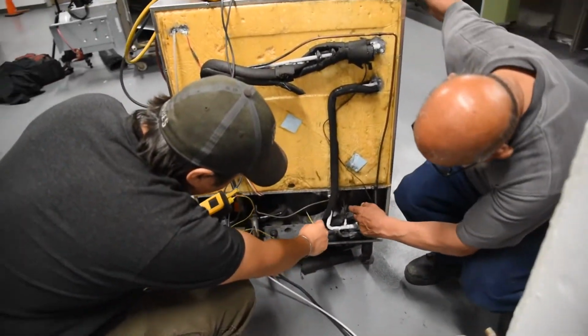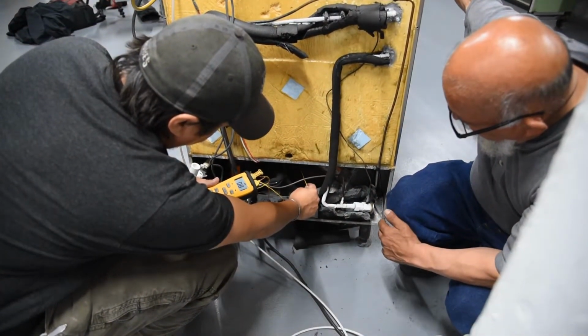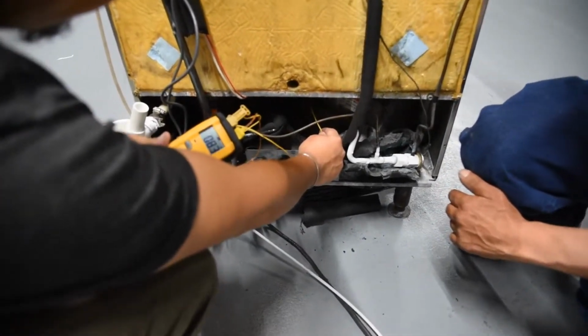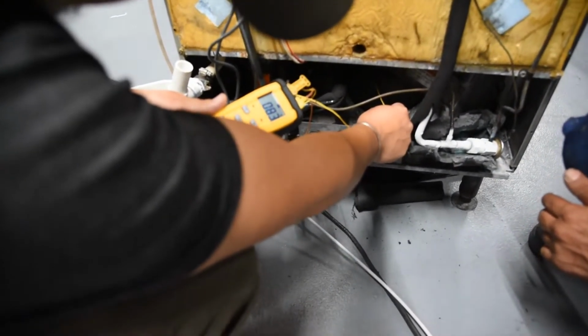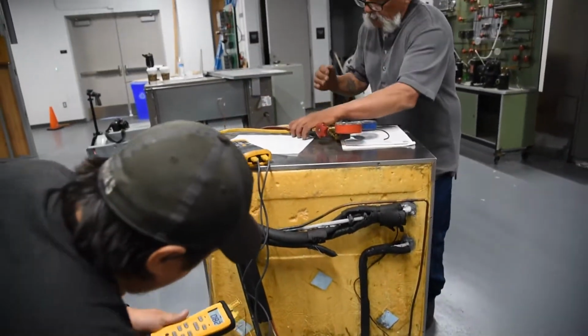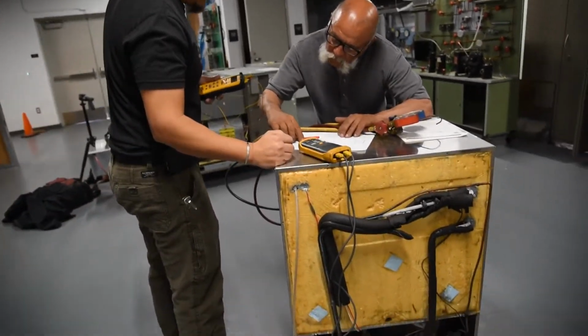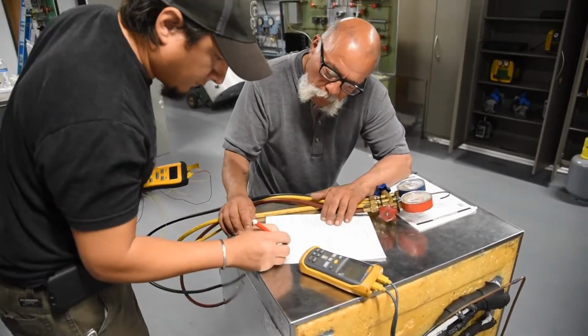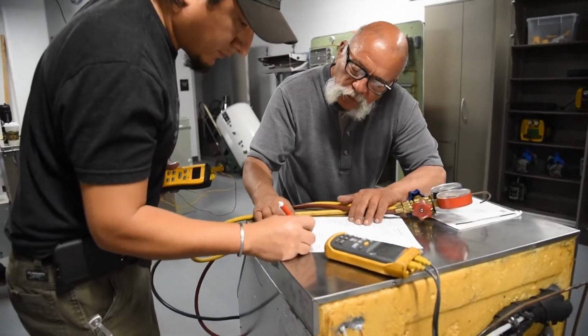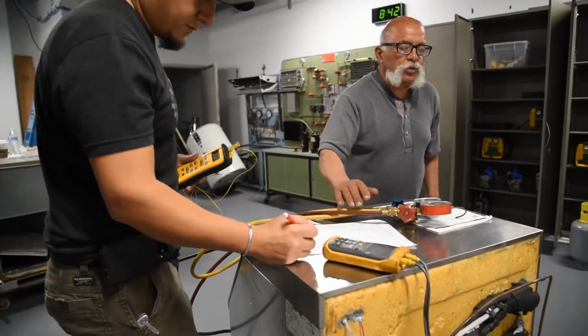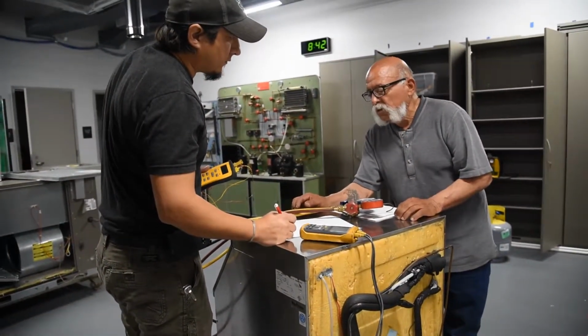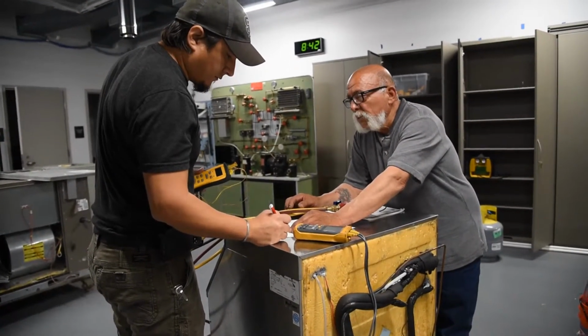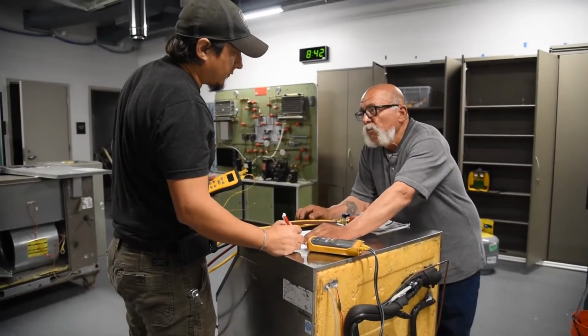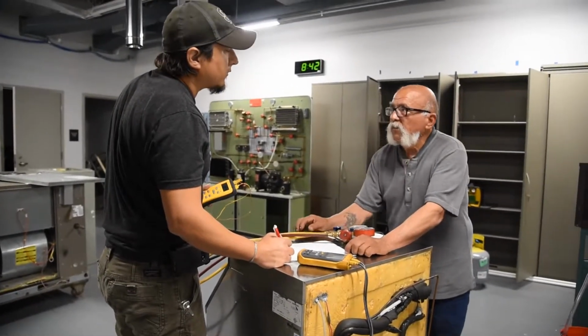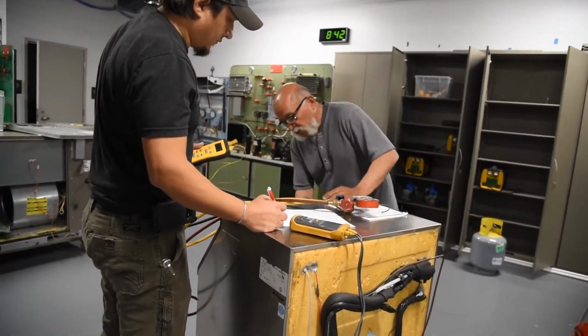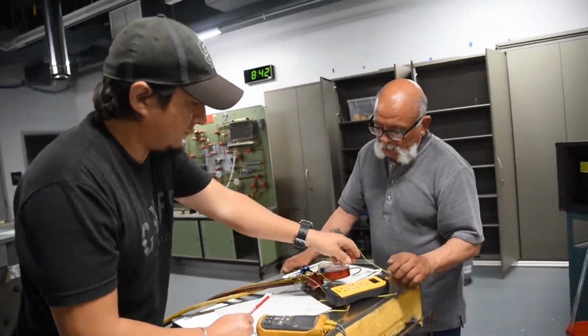You for the condenser? Says 83. 83. So the entering air on the condenser is right there, 73. And leaving is 83. Now I said that the temperature differential across the condenser, general rule of thumb, is about 20. This is 10. That low temperature differential across the condenser is telling us there's not much of a heat load on the low side, on the suction side. Okay. And the reason there's not much of an airflow is because we got that ice building up in there. So that might even go down lower.